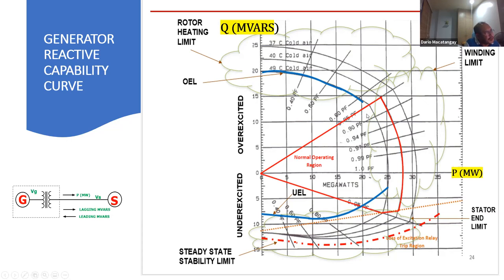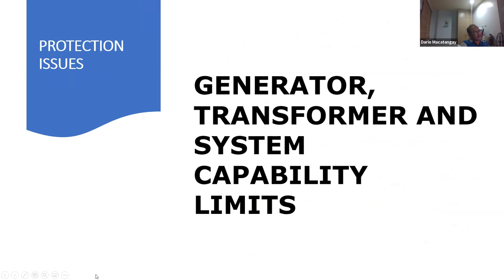Now, this portion here is your stator winding limit. And this area here, coming down, is what they call your stator end limit. The stator end is at the end of the stator. Usually, it has something to do with the leakage flux. This here is your steady state stability limit. When you reach the limit, then you lose synchronism.